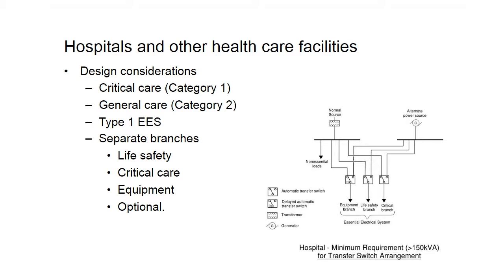So the redundancy and the reliability of the electrical distribution system starts not just with the emergency side, but really with the normal service. This too can be made as reliable as possible, and oftentimes this is done through using multiple sources from the utility or service provider. This could be multiple feeders coming from different substations, different feeder pathways to the site of the facility, in different arrangements within the distribution of the utility or the end user that allows for flexibility, for growth, for routine maintenance, and in testing and eventually replacement. That's often something that's overlooked in the process. And the longer you work in the industry, you eventually have to deal with replacing of equipment, and you want to make sure you've taken that into consideration as you go through the process as well.